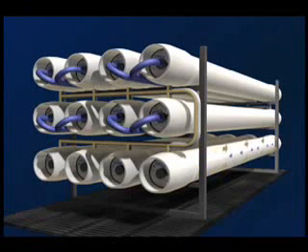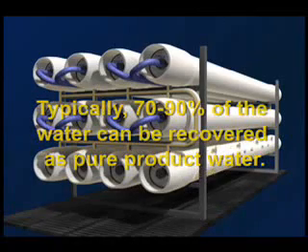The permeate water then flows out the end of the vessel and is collected as the product. The reject or concentrate from that vessel may then flow through another vessel producing more permeate. The remaining concentrate may then be disposed of as waste or partially recycled as the feed. Typically 70-90% of the water can be recovered as pure product water.